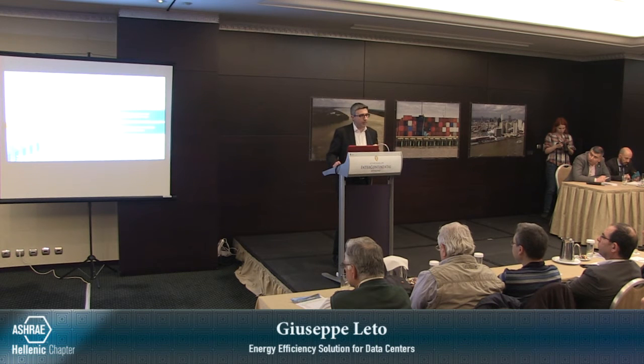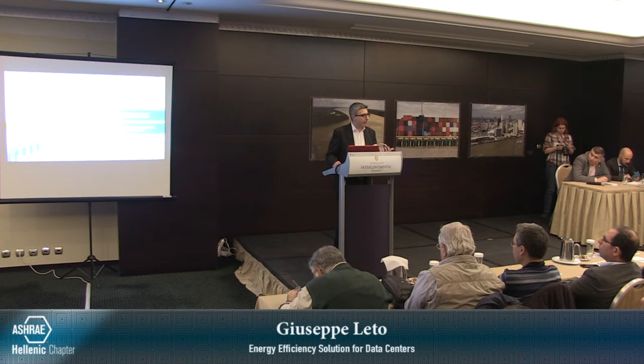Many of you as consultants have to deal with your customers and advise them on what is best to do: changing the cooling infrastructure or adapting it with new technologies. Software is the best at it. So essentially, we moved from a static approach to managing cooling infrastructure to a dynamic one, where all the cooling units are managed differently with different set points. You see one of them is also switched off because it's not necessary. One is running at 100% of its capacity.